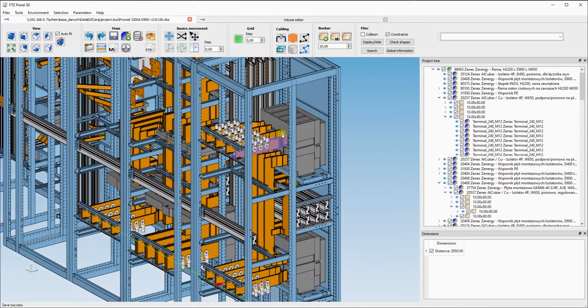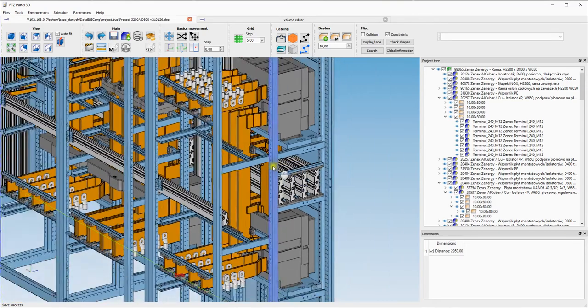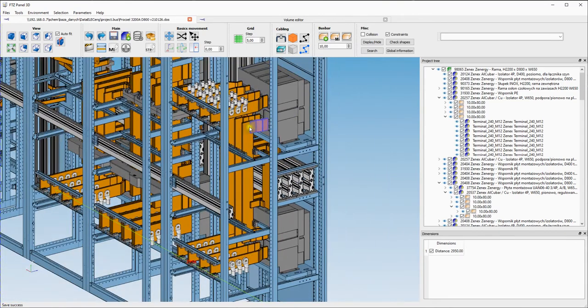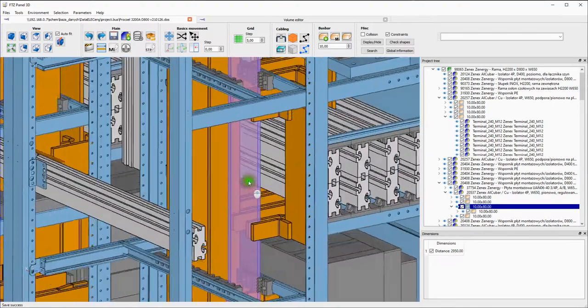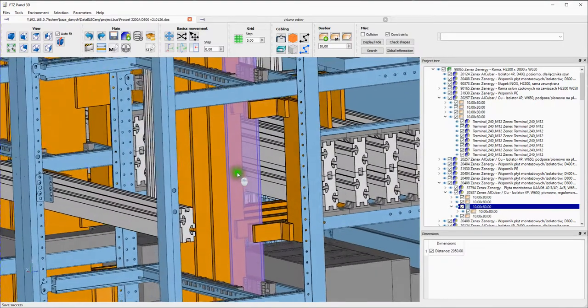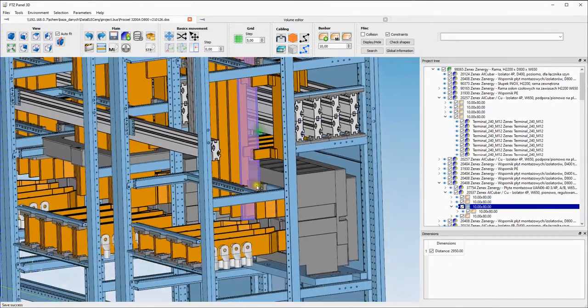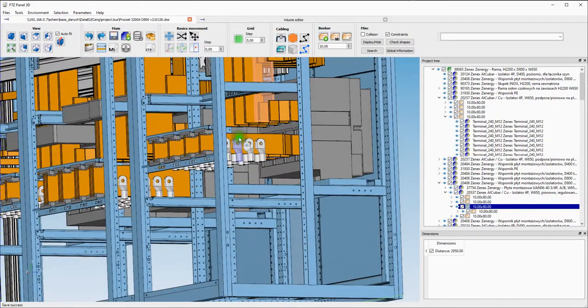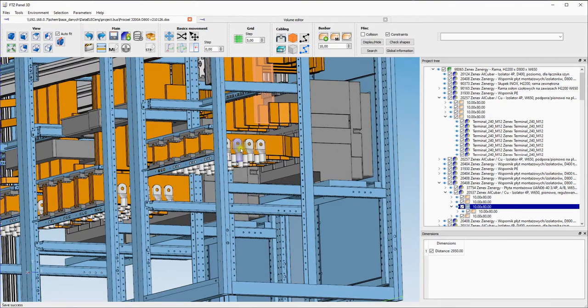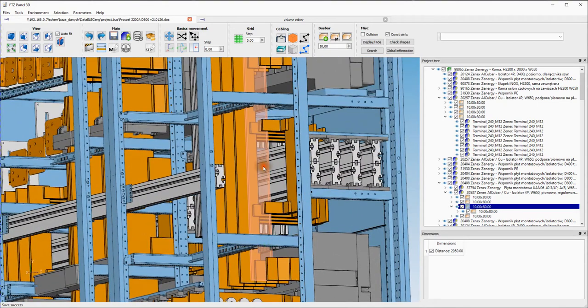It is nicely done that for the main 3200 bus bars, the breakers have the same bus bar. So from the breaker it goes to the main bus duct, and below it is the same situation: the breaker from the bottom supplies the same bus bar.